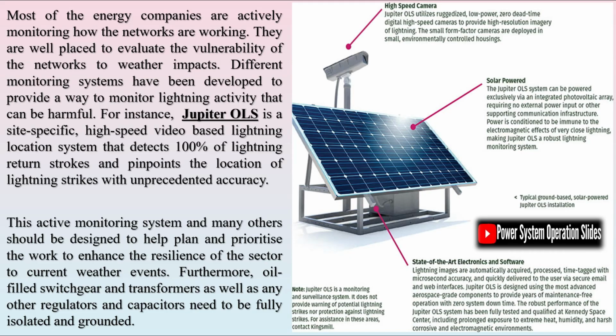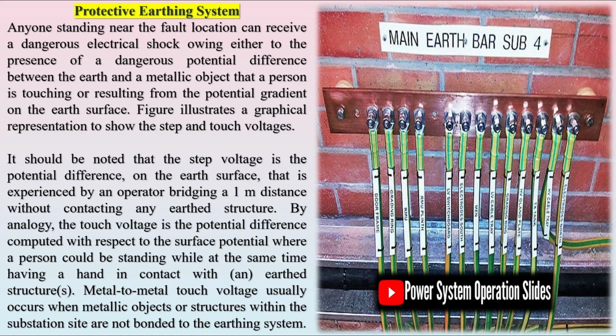Basically, a substation includes different components where the main one is the transformers, used to adjust the voltage levels. This can be achieved by changing the voltage levels between high transmission voltages and lower distribution voltages, or at the interconnection of two different transmission voltages. Substations generally have switching, protection and control equipment, including measurement and monitoring equipment.